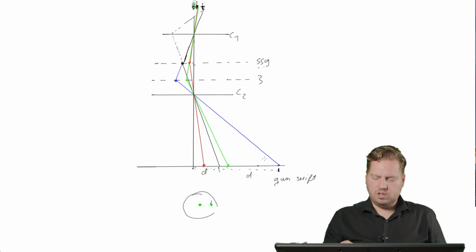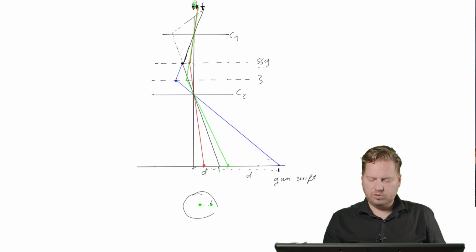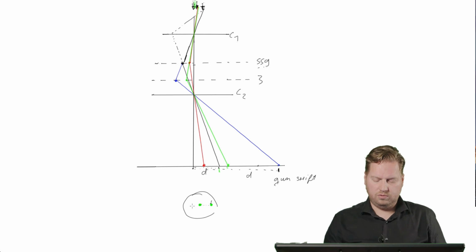Now you can also do this in the gun alignment routine, where you are guided through the routine and it will tell you in a specific step to bring the beam to the center of the flu screen. And you might notice that the microscope toggles between two spot sizes. So again, effectively this is what you're doing. It will also tell you that this step will iterate until the shift is small. So the microscope itself in this routine will determine, because we know when it is good enough, when to stop. If you do this yourself, then you have to decide when to stop.